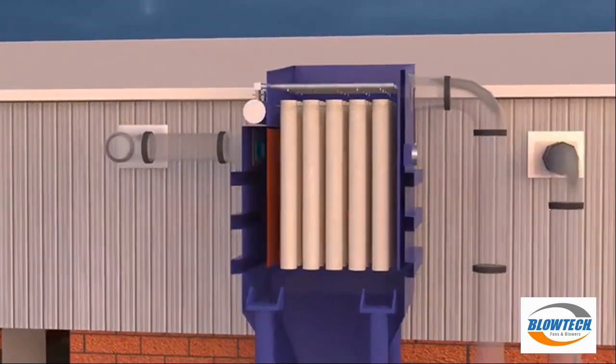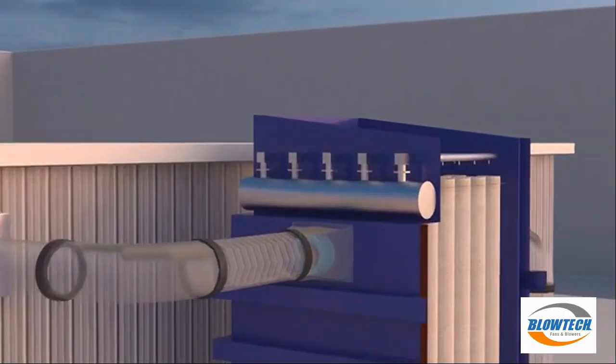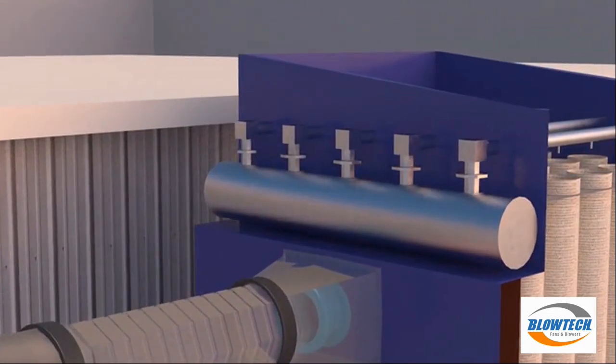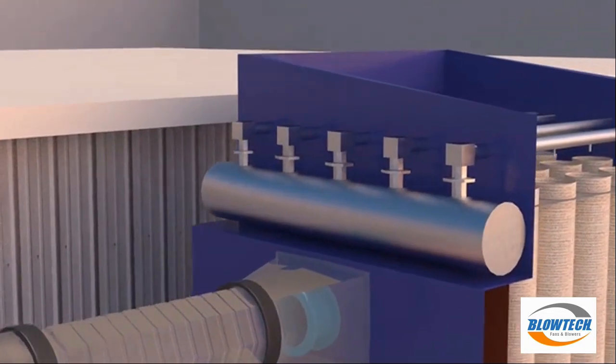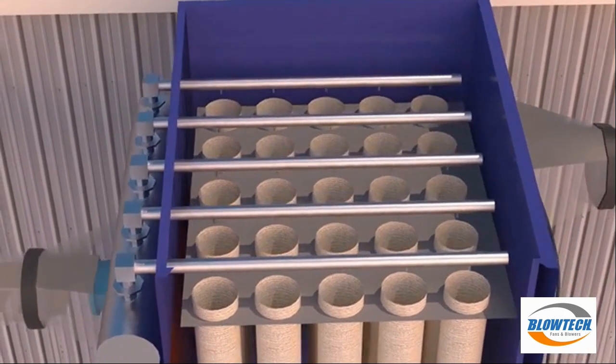Air stored in the header is released, which is carried by the blow pipes. This high-pressure air is then released in the filter bags, one row at a time.